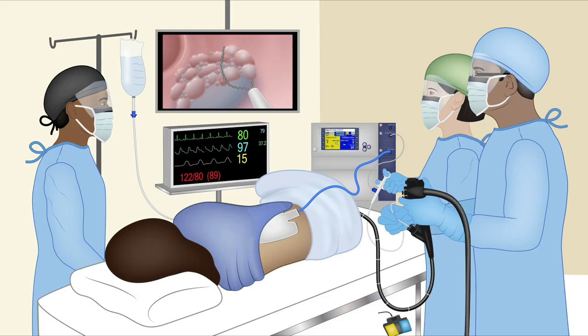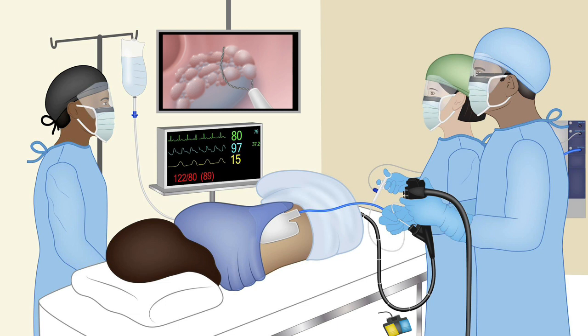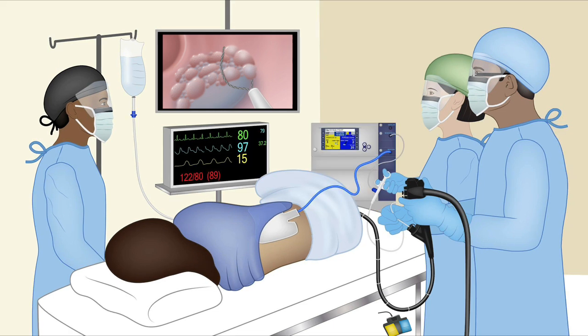One thing that is important in electrosurgery is to make sure that you have your electrosurgical unit right in front of your eyes, not hiding behind all of you. It's very important to keep it right in front so that we can check what parameters are being used before we deliver the current. So, important to make sure to bring the electrosurgery unit right in front of our eyes. That is the most important thing to keep in mind. Otherwise, physicians can deliver the wrong current to the patient. So, before we deliver current, we want to check and make sure the parameters are what we want and deliver the right electrosurgery current.